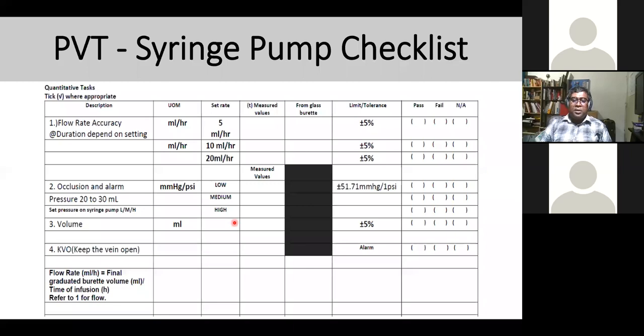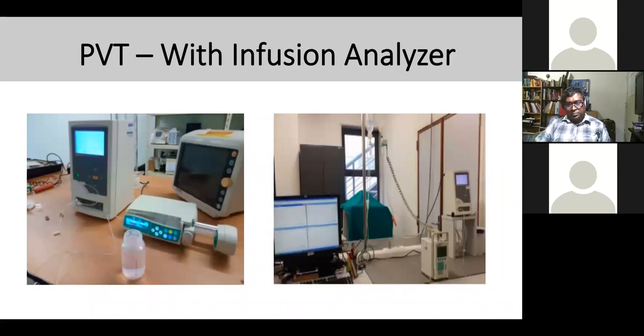KVO is keep the vein open. Normally, this particular part happens when the fluid is completely finished and it's going to give you an alarm of KVO. Okay, so this is what normally we use to test the syringe pump. And with the infusion analyzer, right here, they have a Fluke analyzer, and you can have quite a lot of brands in the market that work the same method. You're going to do flow and occlusion pressure, all this, and bubble, all this. So the step will be like, do the connection, all that, and you apply the tubing with the fluid. You have to prime the line carefully.